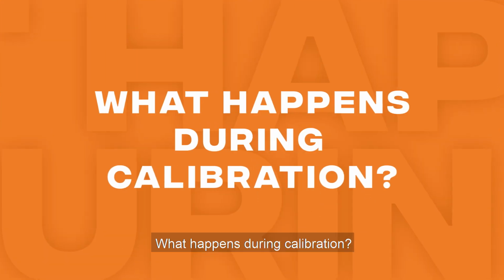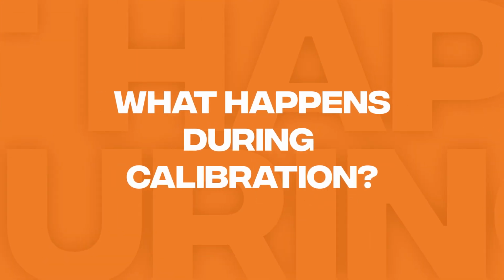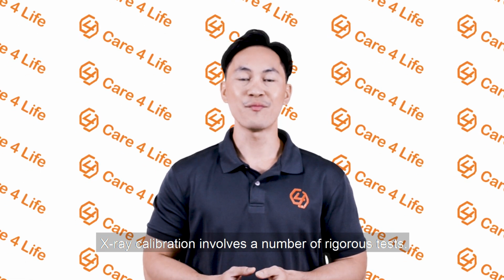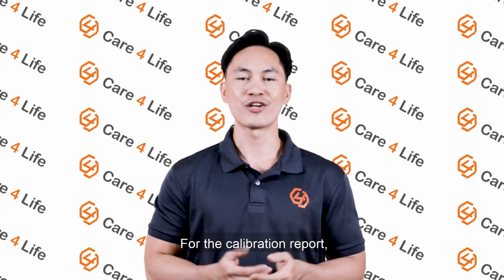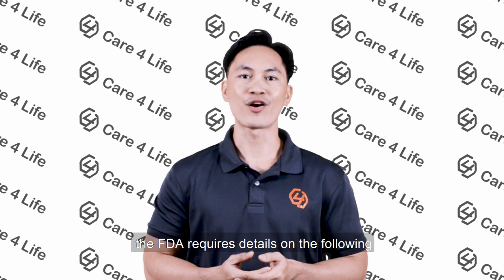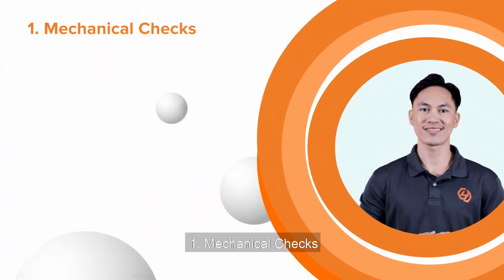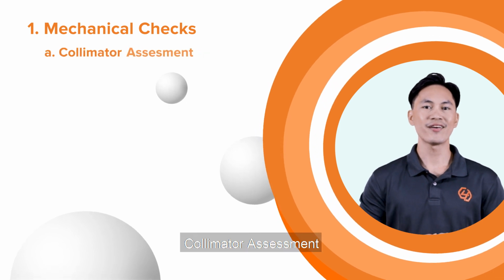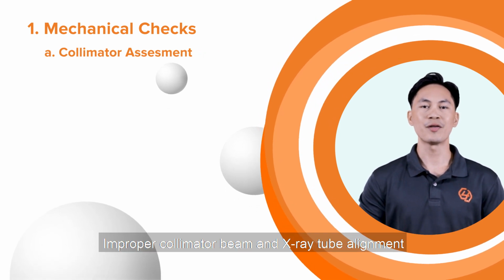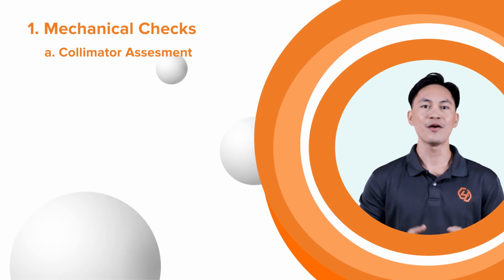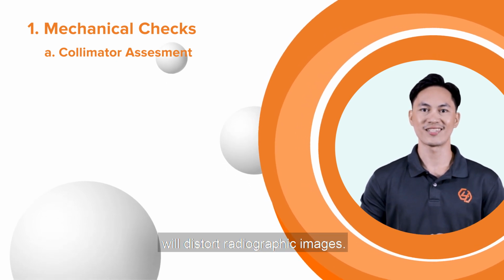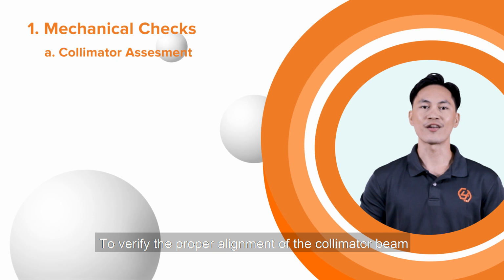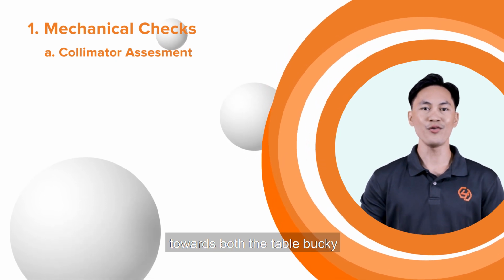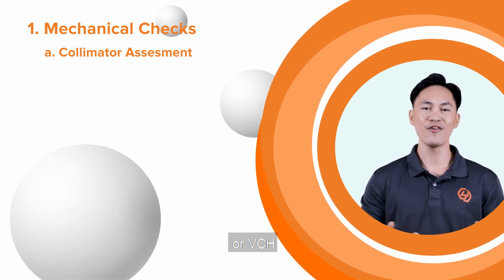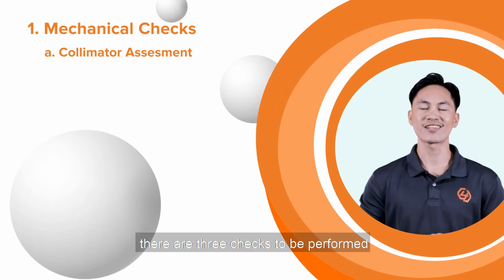What happens during calibration? X-ray calibration involves a number of rigorous tests for the calibration report. The FDA requires details on the following. Number 1. Mechanical checks. A. Collimator assessment. Improper collimator beam and X-ray tube alignment will distort radiographic images. To verify the proper alignment of the collimator beam towards both the table Bucky and Bucky stand or VCH, there are 3 checks to be performed.